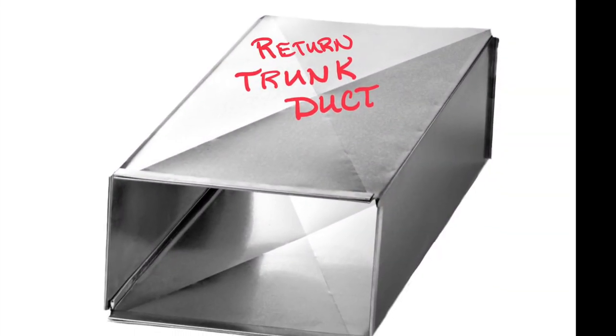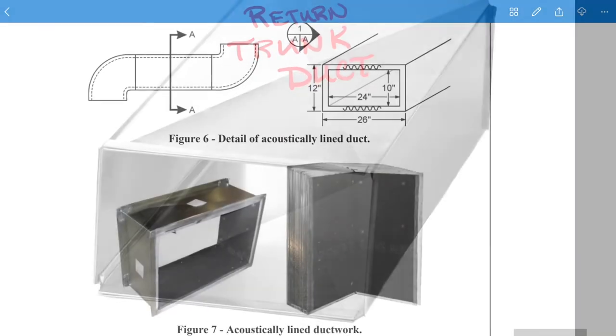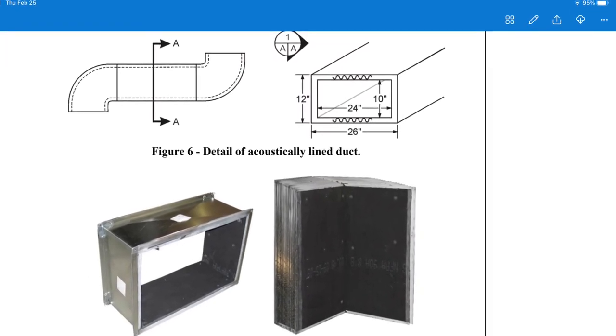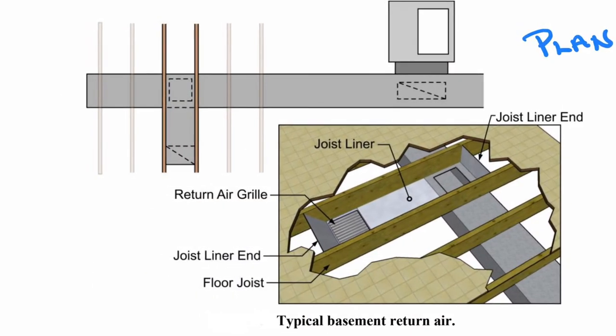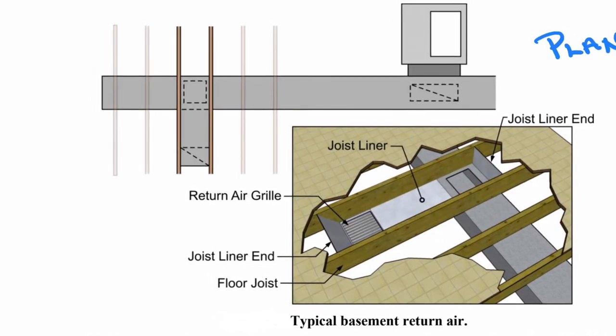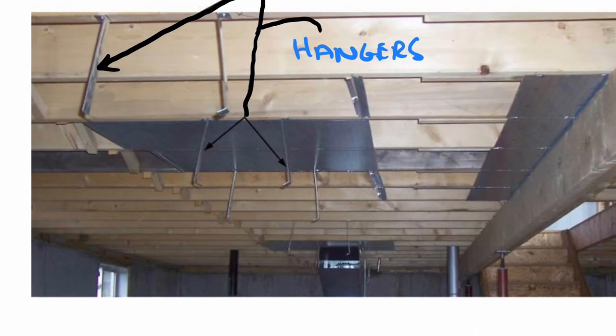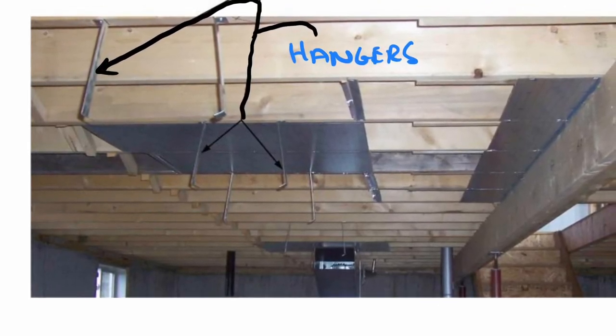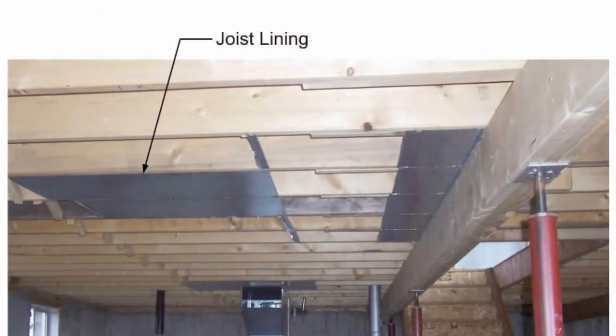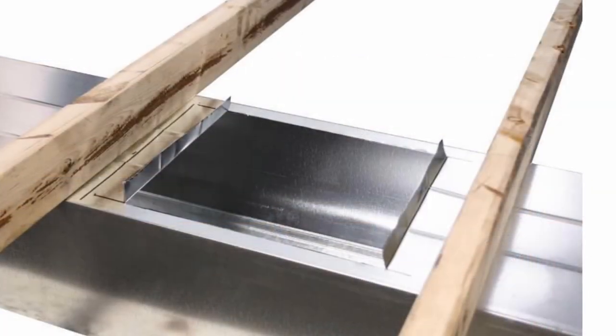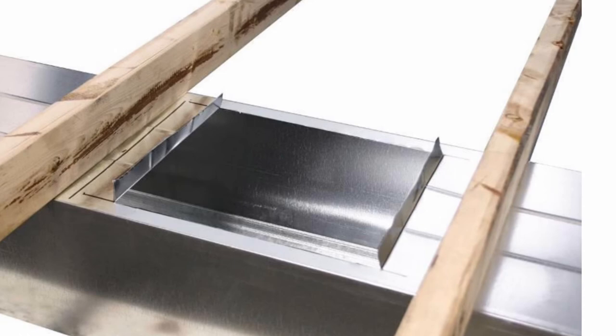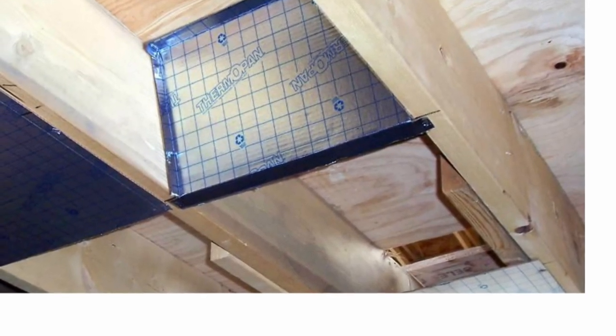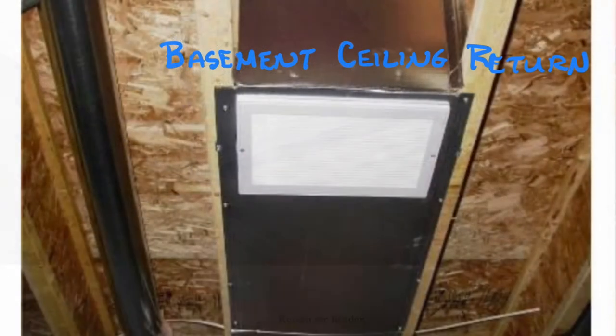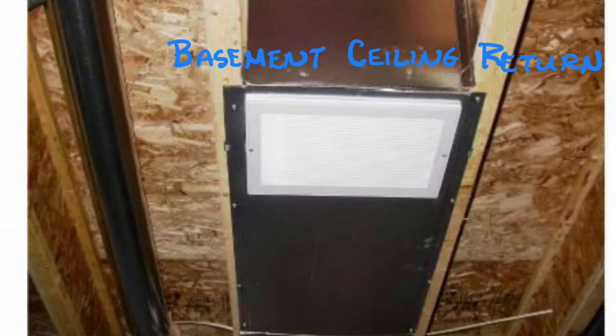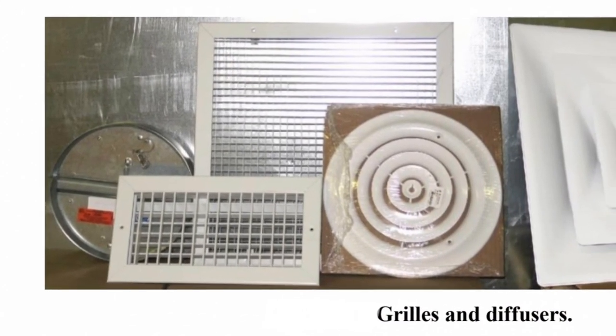Now for the return, you are also going to need to install duct hangers to keep your duct in place. Some of this duct may be insulated. On the return, before running your trunk duct, you will be required to figure out where your joist liner is, or you're going to need to install your joist liner first. And then once the panning is installed, you can now run your ductwork underneath the panning with a hole similar to this. This will connect to the bottom of the panning and create a return air duct. After that is done, you can install a grill for the basement or even grills in the floor on the main level.